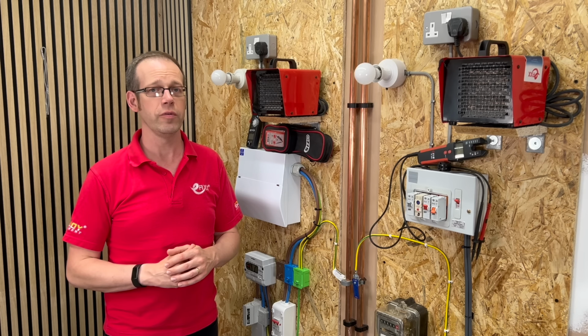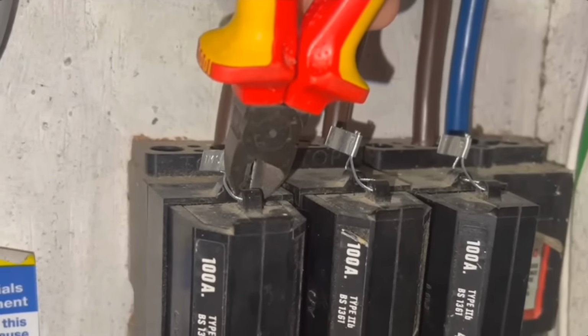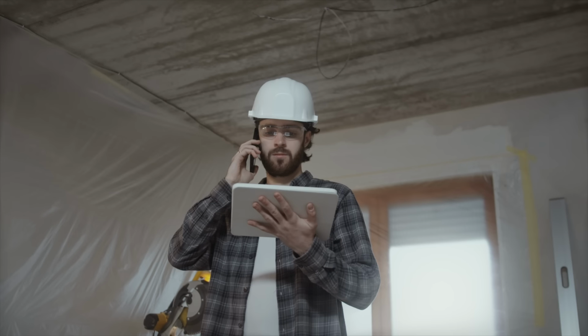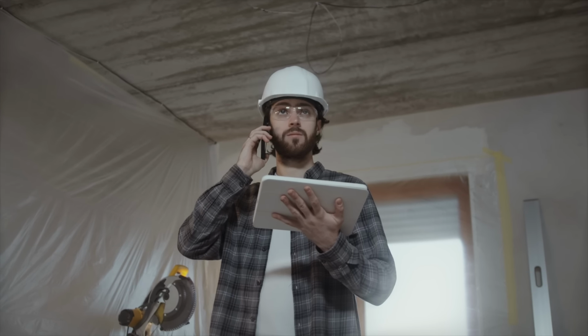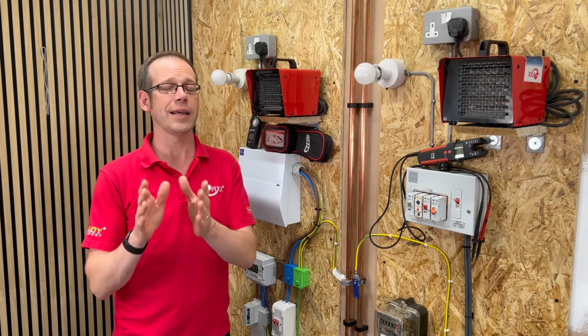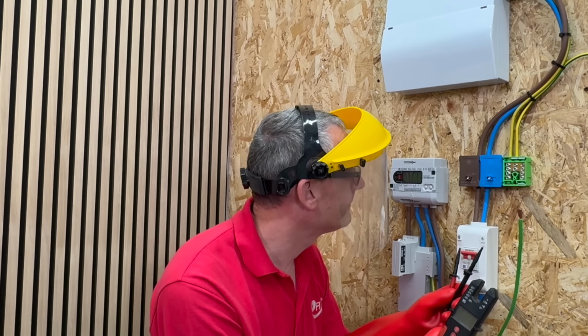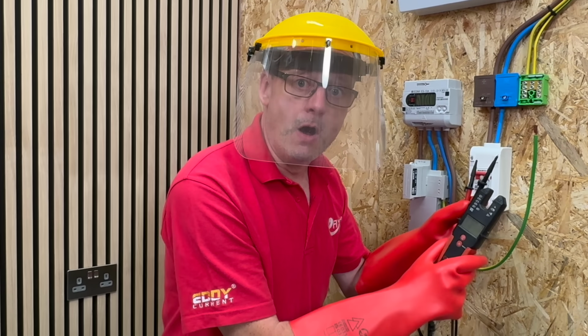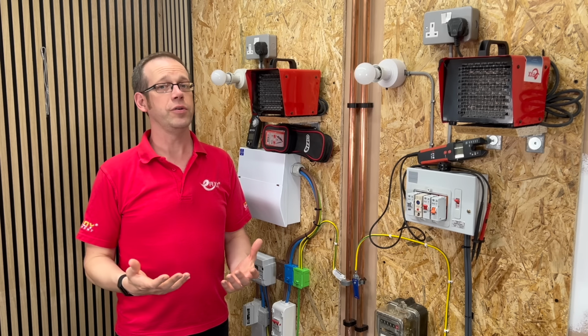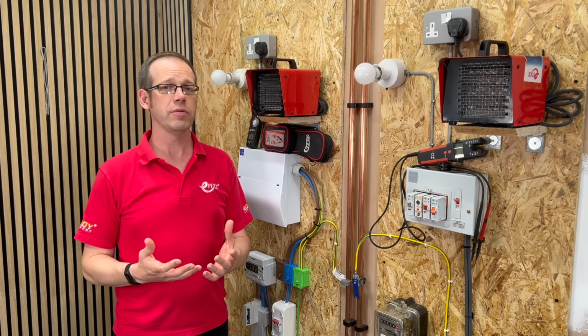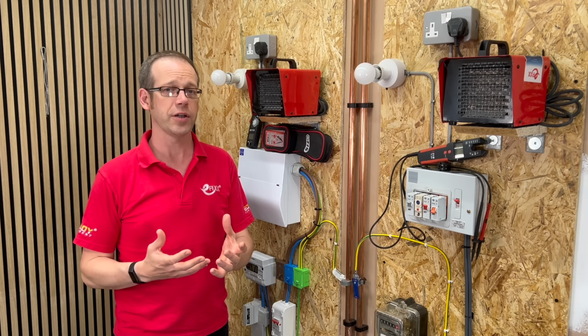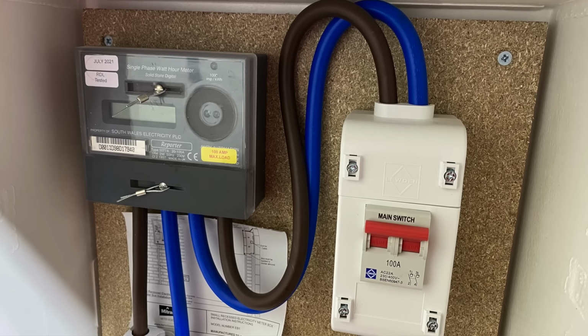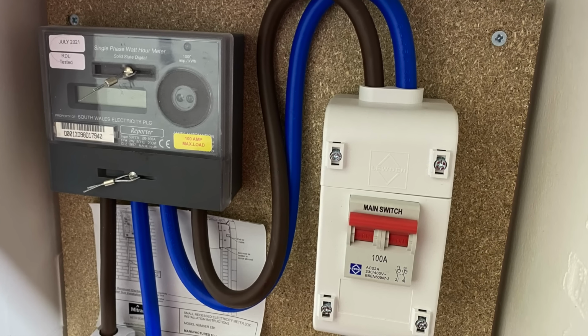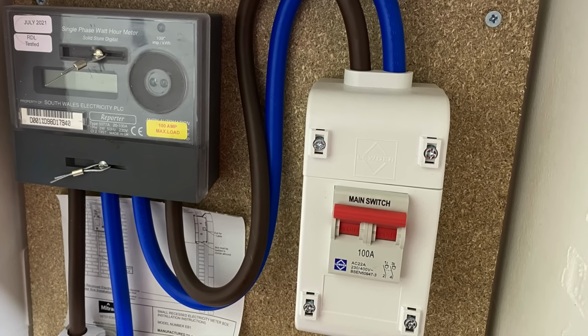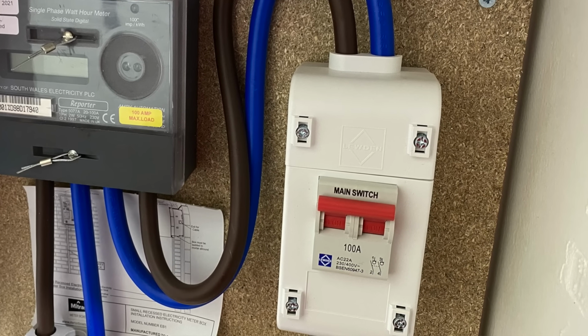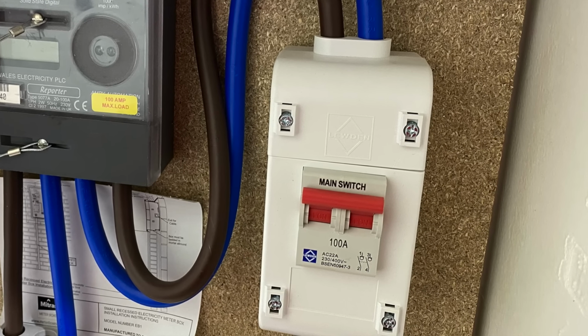You mustn't attempt to remove or alter DSO-owned service heads or seals. If a defect or hazard is suspected, report it to the relevant DSO. They are responsible for addressing service head issues, including fuse replacement and component integrity. When you're working near the intake, you should always use Class 2 insulated tools, arc-rated gloves and safety glasses. Even with the main fuse in place, faults in degraded service heads can result in arc flashes or unintentional energization of nearby equipment. Where permitted and coordinated with the DNO, installing an accessible double pole isolation switch downstream of the meter is a highly recommended practice. This allows safe isolation of the customer's installation without disturbing DSO equipment.